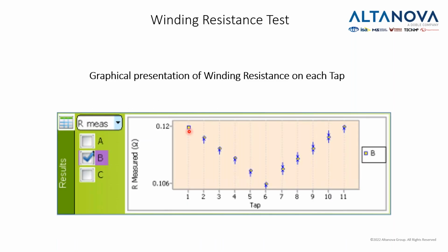We also need to keep in mind that if we don't have the values from the factory, we can always compare phases. So the key thing is the difference between phases cannot be more than 2%. In some cases, maybe 3%. And that also applies to the comparison with the nominal values. The difference cannot be more than 2 to 3% from the nominal values.